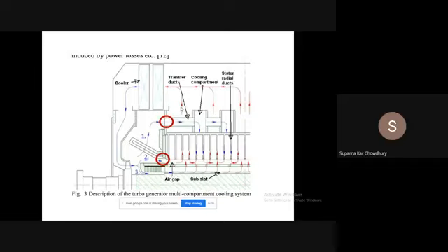If oxygen is not there in sufficient quantity, it cannot explode. But the system should be totally leak proof. Normally the pressure inside the cooling system is kept high so that no air can get into the system from outside, and there are indicators which indicate the oxygen content of the coolant inside.